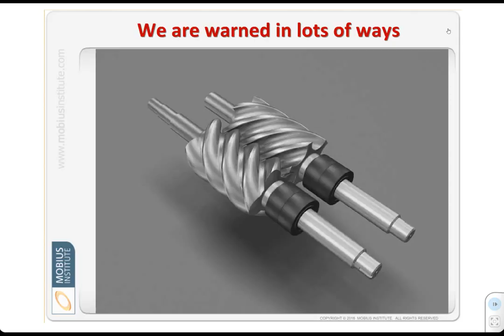And we can, for example, detect temperature changes. So we can use our infrared cameras and other tools, but we can see the signs of changes in temperature. So we can see electrical problems, mechanical problems, issues with flow, what's happening in tanks, what's happening with steam traps, all sorts of things by measuring temperature. With our electric motors, we can tell if there are supply problems to the motor, like voltage with harmonics. We can see imbalances in voltage across the three phases. We can see if there's problems with the connectors, with the stator, with the rotor, broken rotor bars, insulation issues. Boy, there's all sorts of tests we can perform on our critical and precious electric motors.